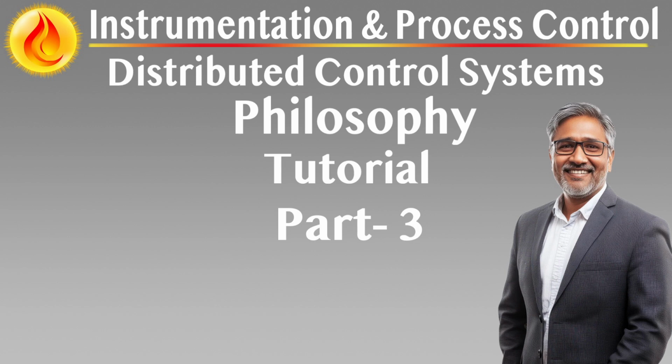Voting logic and zone isolation. 2oo3 voting is applied where required to eliminate false positives. Detection zones are configured for independent control of fire suppression, ventilation isolation, and shutdown command propagation.